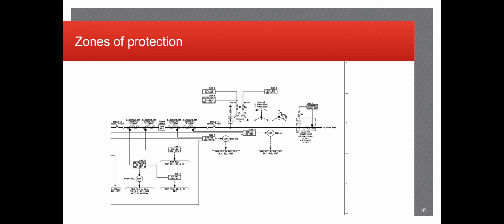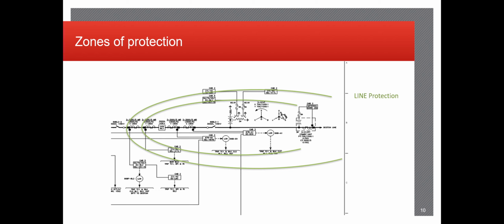So we're going to go over the zones of protection for this specific section of lines. We are going to be identifying the zones of protection for the Boston line relay. So the first section is going to be our line protection zone. Those relays, the primary and backup, should be covering anything that's on the line going out to Boston, any breakers, CCVTs, anything like that, any major equipment that should be looked at. The breaker itself off to the left, the BL2 breaker, is going to be our main source of protecting the line in case of a fault.